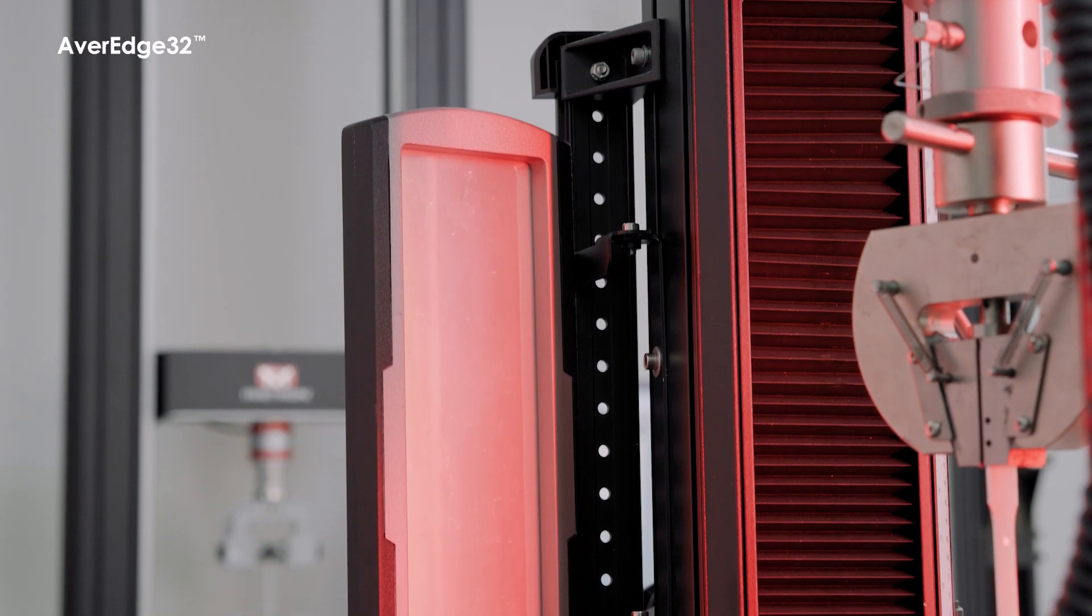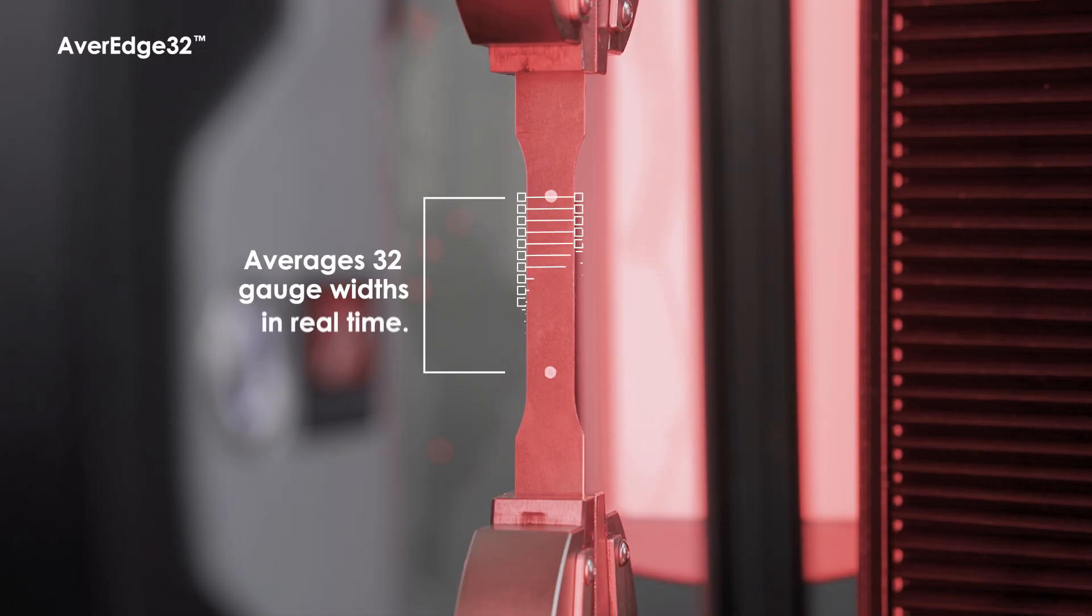For those requiring R-value or plastic strain ratio measurement, the optional AverEdge32 feature provides best-in-class transverse strain accuracy by averaging 32 measurements from within the specimen gauge length.